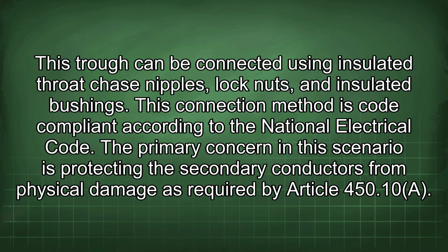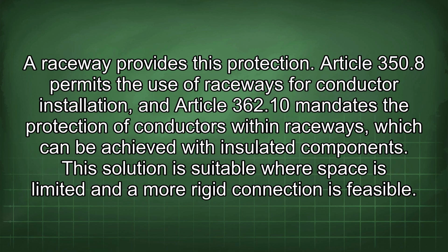The primary concern in this scenario is protecting the secondary conductors from physical damage as required by Article 450.10(A). A raceway provides this protection. Article 350.8 permits the use of raceways for conductor installation, and Article 362.10 mandates the protection of conductors within raceways, which can be achieved with insulated components. This solution is suitable where space is limited and a more rigid connection is feasible.